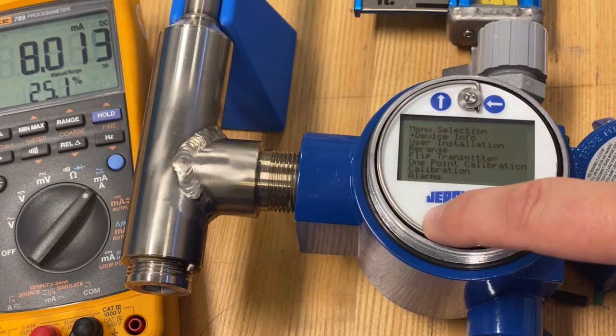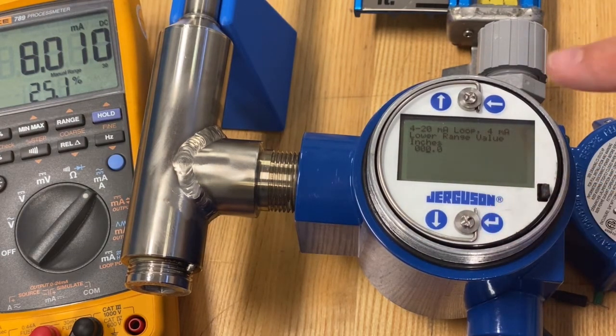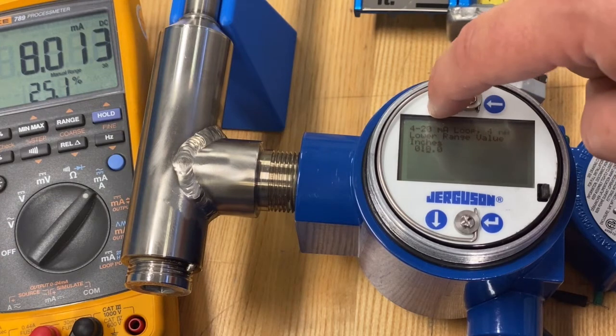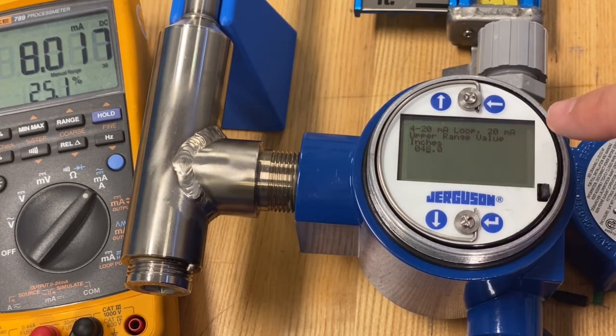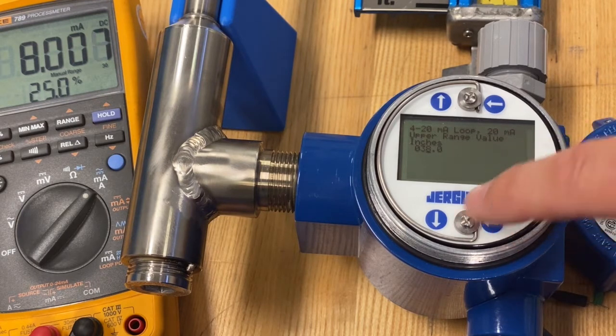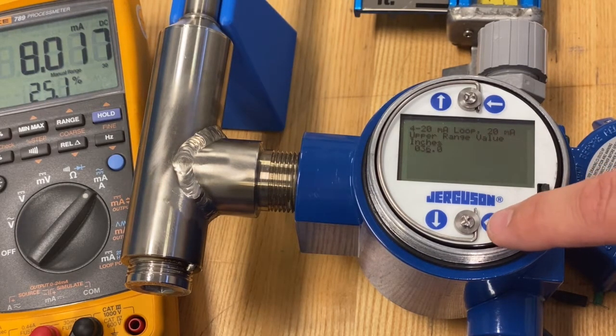Enter the menu and scroll down to find the rerange function. The first question it asks is where do you want your 4 milliamp? I'll press the up button — I can press up 12 times or modify the tens, which I'll show on the next screen. I set this at 12 inches. Enter to clear the menu, then go to the 20 milliamp option. Going back to the tens, hit down, enter to get back into the ones, down two more times. I'm going to set 20 milliamp — 100 percent or full — to be at 36 inches, giving this a 24-inch span.